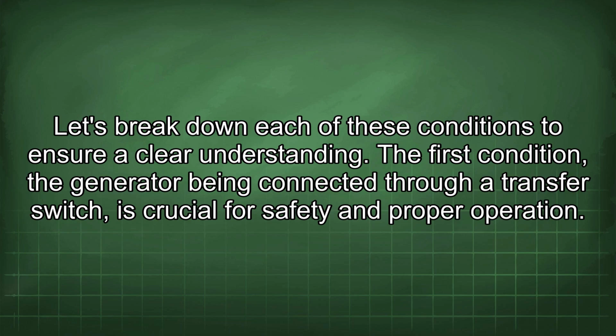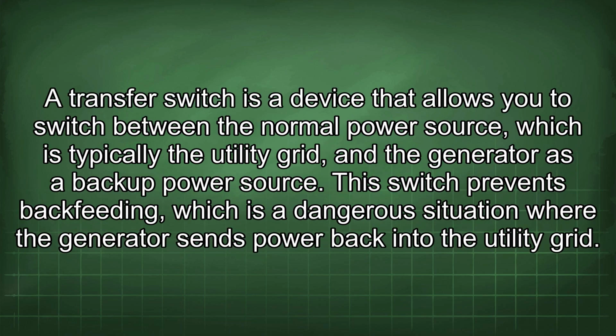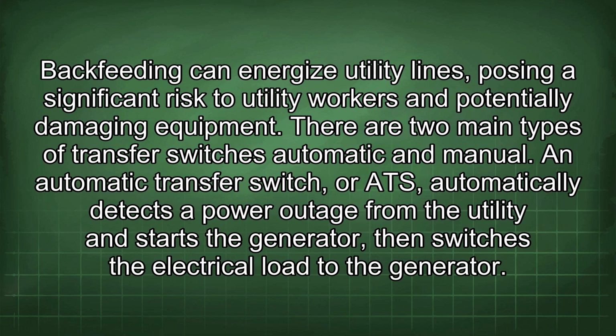The first condition, the generator being connected through a transfer switch, is crucial for safety and proper operation. A transfer switch is a device that allows you to switch between the normal power source, which is typically the utility grid, and the generator as a backup power source. This switch prevents backfeeding, which is a dangerous situation where the generator sends power back into the utility grid. Backfeeding can energize utility lines, posing a significant risk to utility workers and potentially damaging equipment.